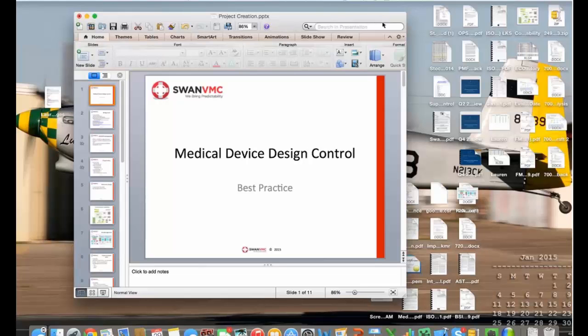First one for you is, how do you handle essential requirements? Okay, so essential requirements are one of the things that we use in the technical file. I think the reason that countries do this is because they want to process the data in a particular way that's the same for all the devices. They're requirements in a way, but what they're asking for is particular pieces of the design control data. And so what I do is I create a work item called an essential requirement work item.